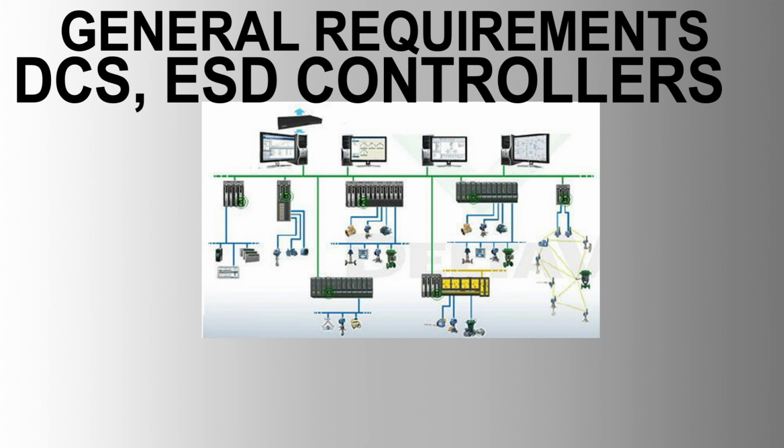7. Various networks in DCS. Control network, utilized for real-time control and monitoring of the process. Ensures fast and reliable communication between controllers, workstations, and I/O devices. I/O network, manages communication between the field devices and controllers. Should not exceed 60% loading, even when all spare capacity in DCS is utilized. Corporate network. Facilitates integration of the DCS with higher-level business systems and applications. Ensures secure and efficient data transfer for business intelligence and decision-making.